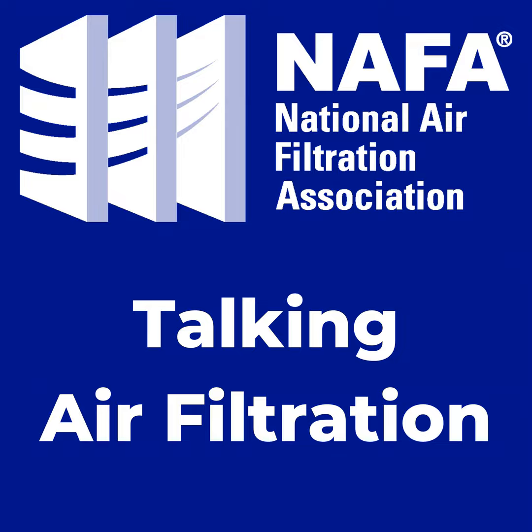But you see here, the electrostatic charge drops from one filter class to another based on dissipating the electrostatic charge. What they actually do is average the initial state and the final state after it was discharged, and you can get an average efficiency with that. So I think it's good to make people more aware of what's actually going on in these filters, and how the filter media efficiency isn't actually what it's advertised to be always.